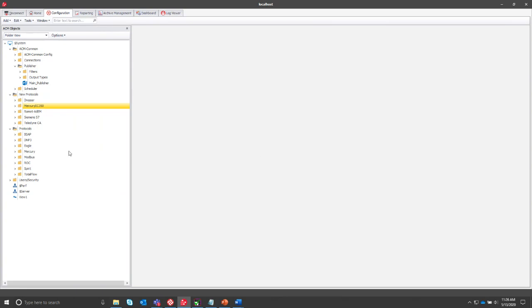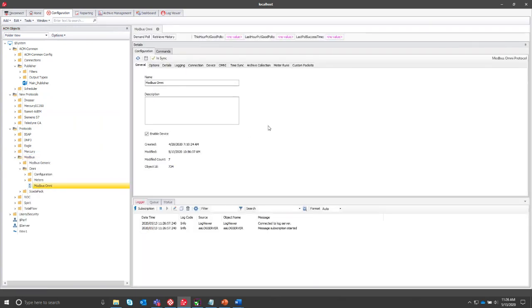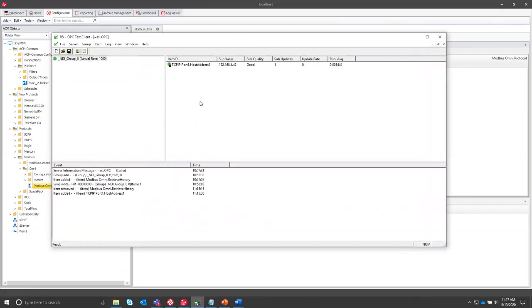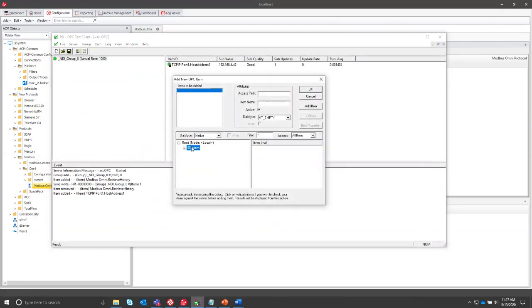To demonstrate this, I'm going to bring up the Modbus Omni and show this using the OPC client. Here we have the logger for the Modbus Omni. I'm going to bring up OPC test and add the item for the OPC test, for the Modbus Omni, to retrieve.